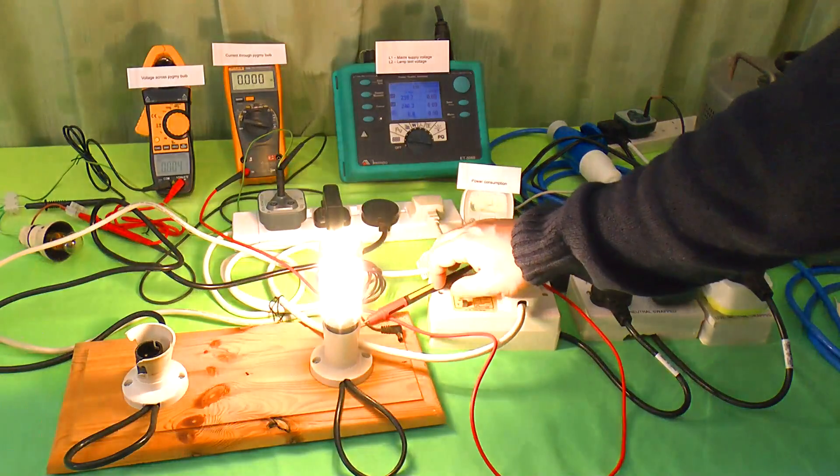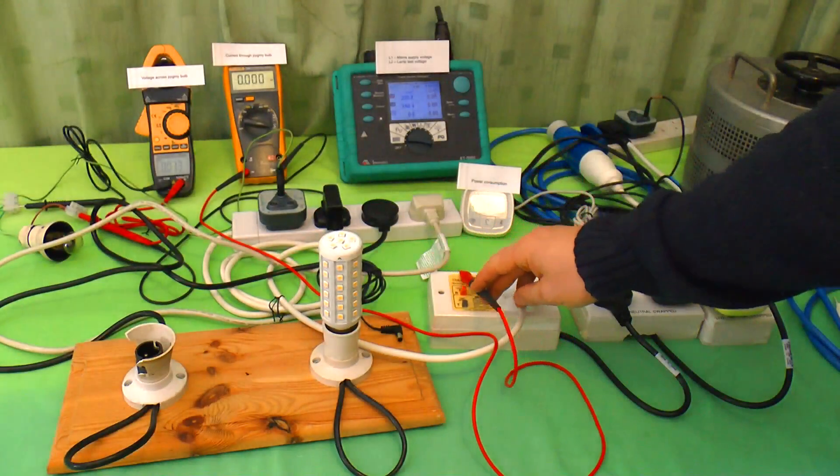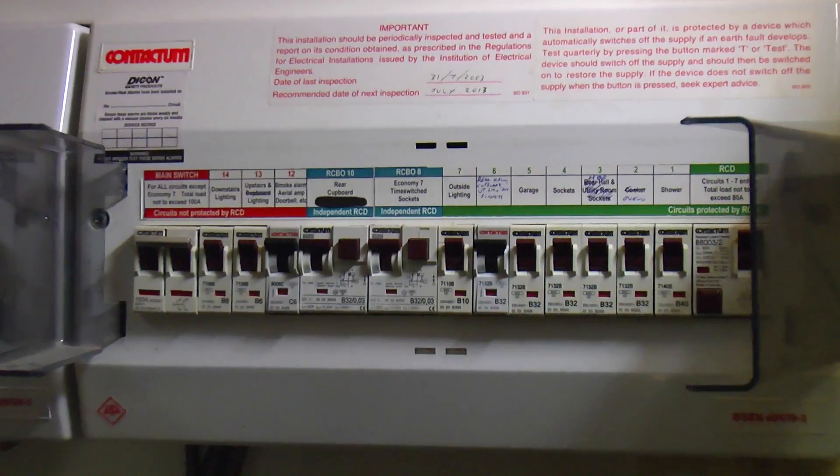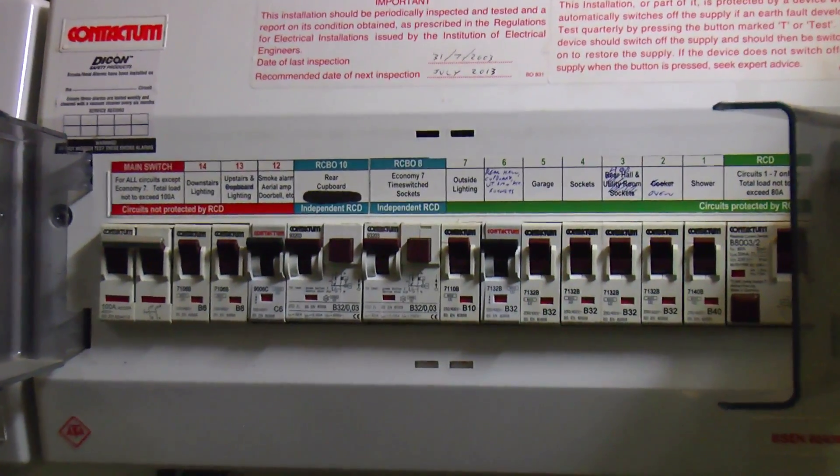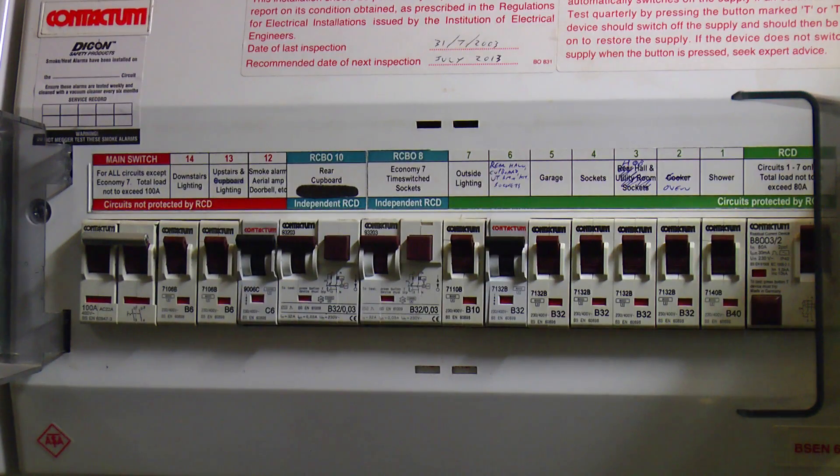So touching one of these lamps while switched on will trigger the RCD and cut the power to limit the severity of an electric shock. But what if there isn't an RCD? Many homes have no RCD protection on the lighting circuit so that a faulty appliance that trips the RCD doesn't plunge the whole place into darkness.